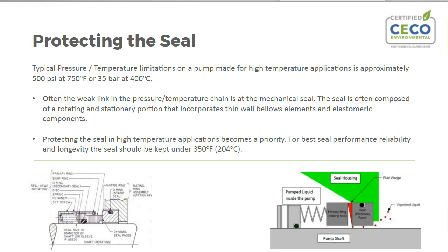So there's generally not a whole lot of worry about the pump failing due to high temperature or pressure. What is problematic, however, is that the seal used to seal these pumps is not designed to handle those incredibly high temperatures and pressures. Oftentimes, it does tend to be the weak link in the pressure temperature chain.